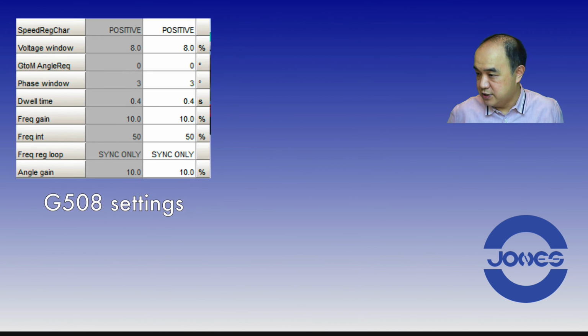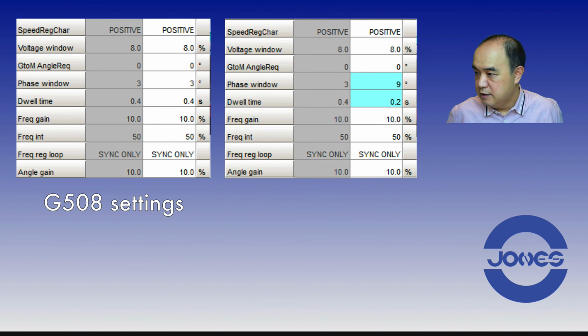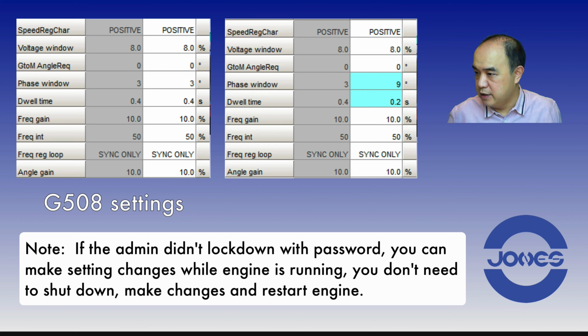So while I was on site, I didn't like the default ComAp settings, so I went on to change the settings. Namely, 8% voltage window, from my experience, is fine. 8%, 10% is not a big difference. The phase window, I changed it to 9 degrees. For myself, I typically like to set it to 8 degrees, but 8, 9, 10 degrees is not a huge difference. You need some angle for this to work.